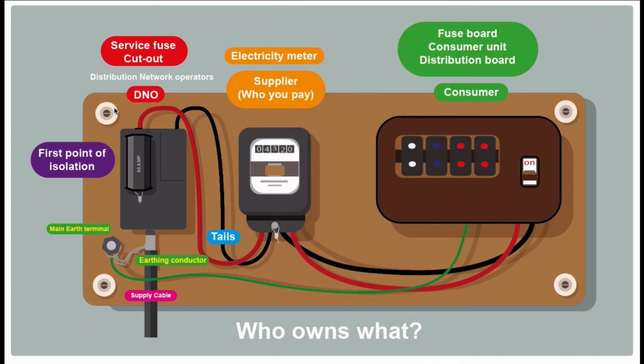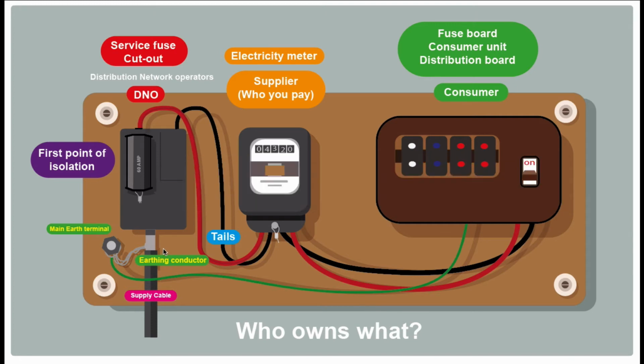and it's not coming away from the wall. Sometimes I see them hanging right off the wall and it's putting strain on the supply cable. Now don't you try and fix that back, don't try and push it back if it is hanging off the wall. Call the DNO, they're responsible for this board and they will come and fix it. Reason being is it's connected to the supply cable, and this supply cable could be 50, 60 or more years old, and it doesn't take kindly to being moved. And if you start pushing this board about trying to bend it back into place, you could cause a short in the cable, and that could cause real problems. So if the board is damaged in any way, get the DNO to come and look at it.